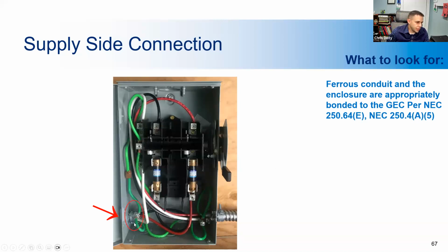The purpose of this is that these are usually connected to the enclosure via knockouts, which are like pre-pushed through, so there's not a huge amount of connection, so it's easy to get out. If there was fault current running through the conductors and it got into the conduit and wanted to get through into the enclosure, it would likely be more than that knockout could hold, and it would melt through and cause damage and potentially a fire. So that's why you separately use these crimp connectors to bond and ground the conduit itself.